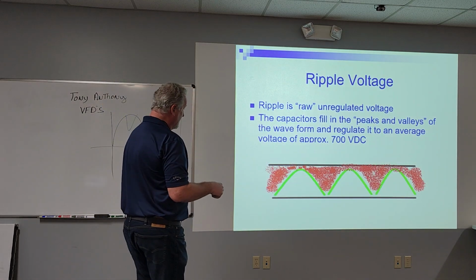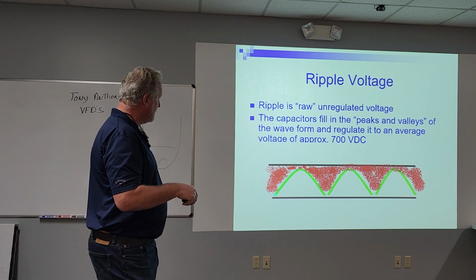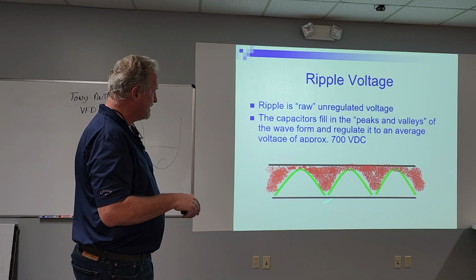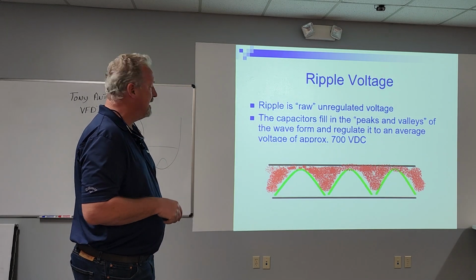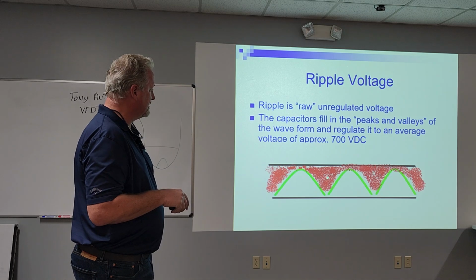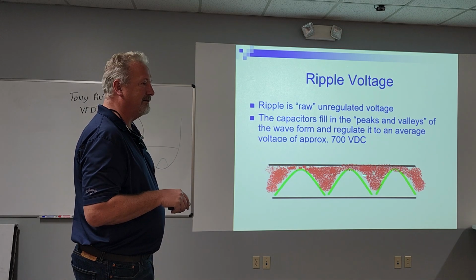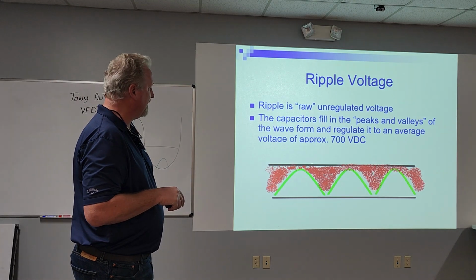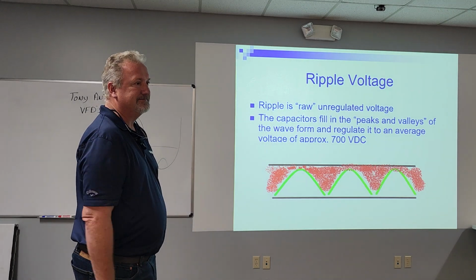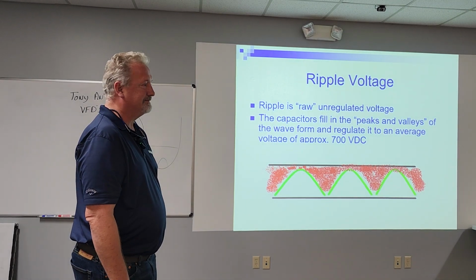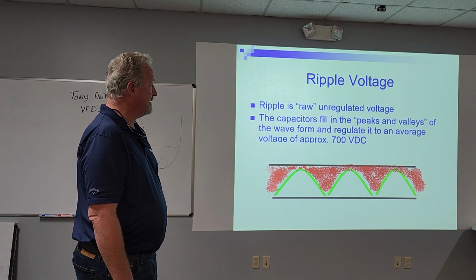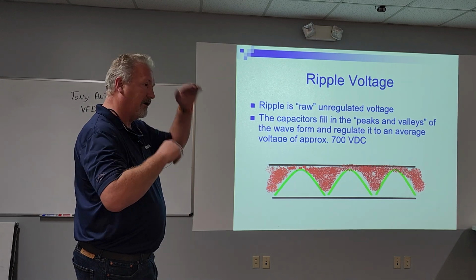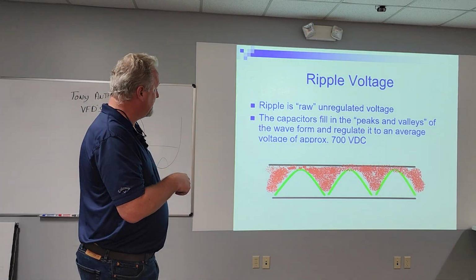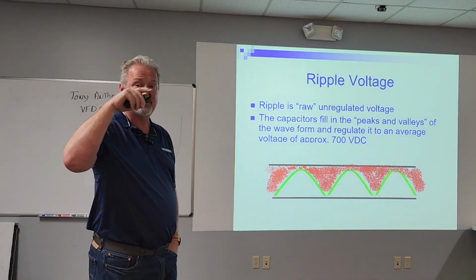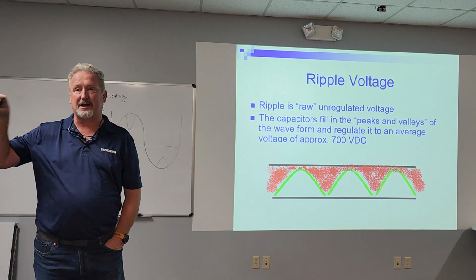So that capacitor, this is what it would look like if we didn't have capacitors. We have this little rippled DC bus. The capacitor charges and discharges continually to fill that little gap in and creates a nice flat DC. So they create the DC bus, they hold the charge for the DC bus, and they also make it a pure DC. They're continually sitting there charging and discharging to fill in that little gap.